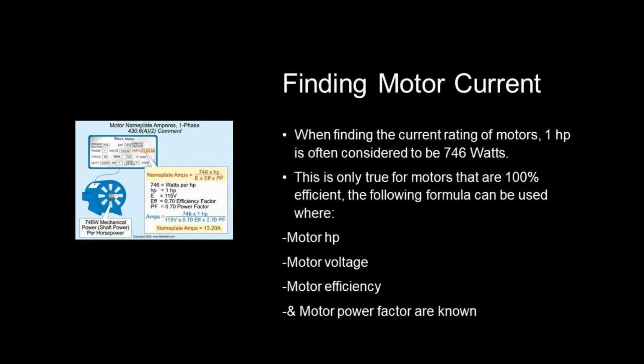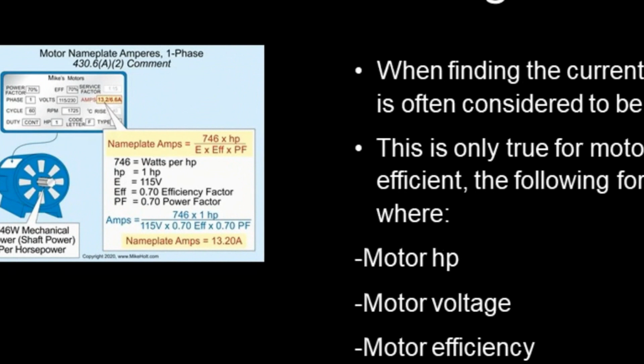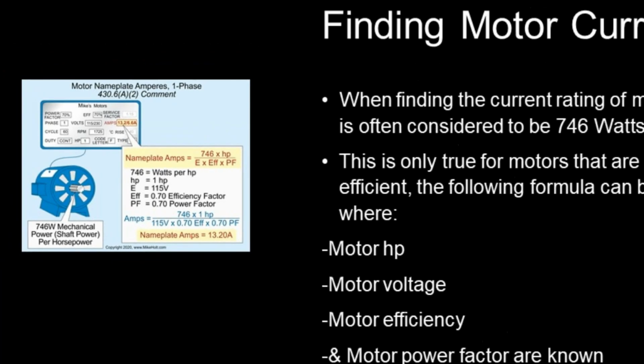All right, so motor current. When finding the motor current rating of a motor, 1 horsepower is considered to be 746 watts. This is only true for motors that are 100% efficient, and therefore we can use this formula. Motor horsepower, voltage, efficiency, and power factor have to be known. So here's my formula. My nameplate amps is going to end up 746 times the amount of horsepower over the voltage times the efficiency times the power factor. And that's how they come up with it, just so you're aware.